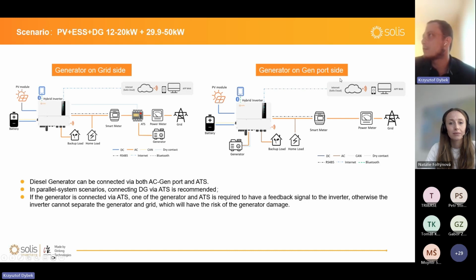And the generator on the Gen port side connected directly to this third, let's say, port, because here we have AC, here we have backup, here we have this generator port. If the generator is connected directly here, there is no problem, to be honest. So the disadvantage is that if you have a grid loss situation, this is cut off totally. There is no home load, only backup load. The battery will discharge to your backup load. If the battery is drained, the generator will be turned on and cover your backup and your battery. After the battery is fully charged, the generator is going to turn off and the battery starts to discharge once again to the backup load. So this is a very safe solution.